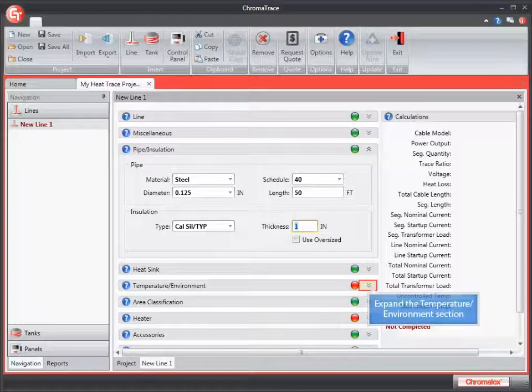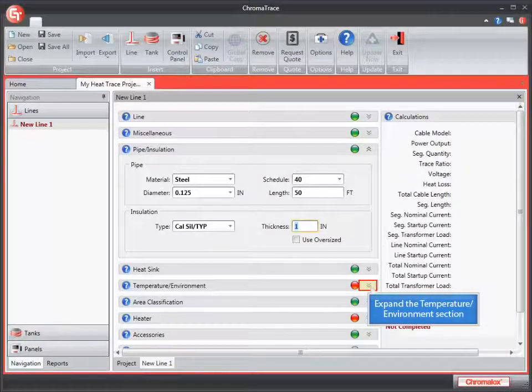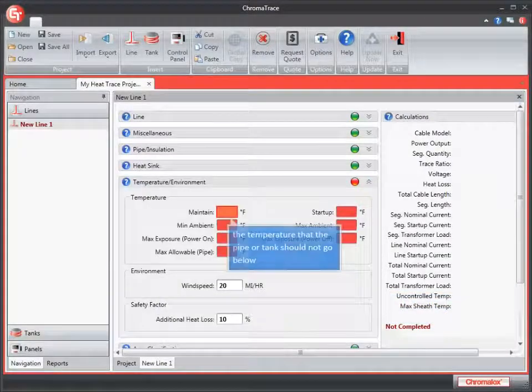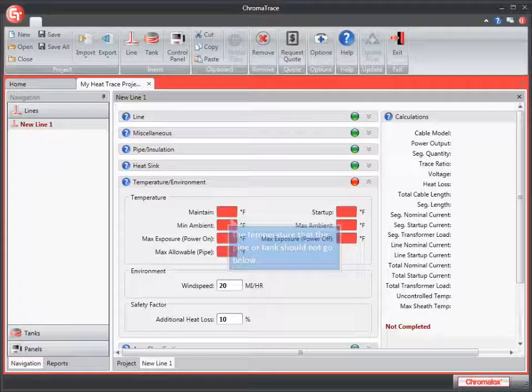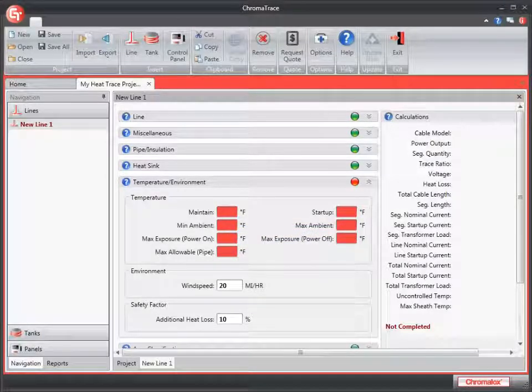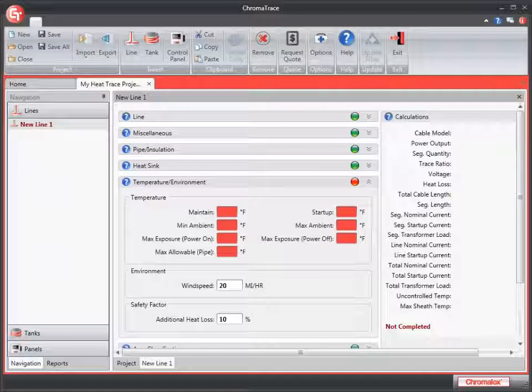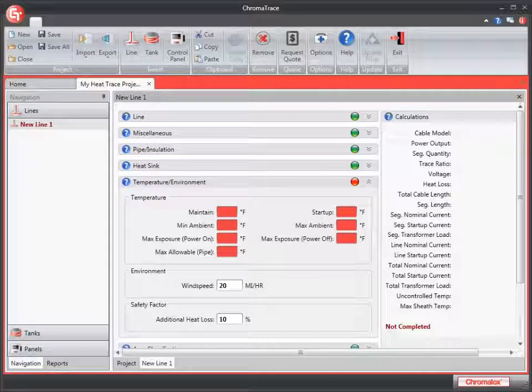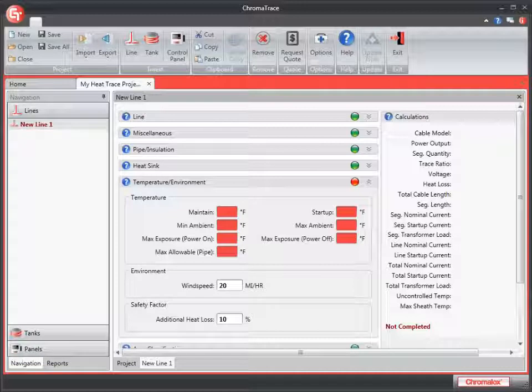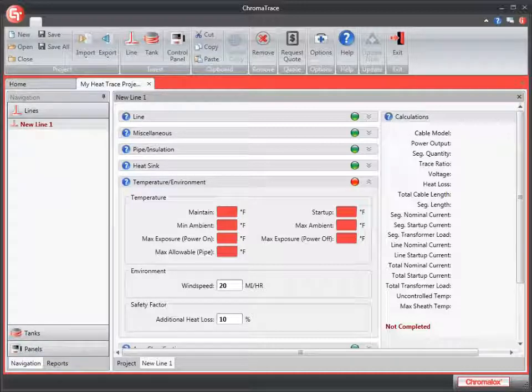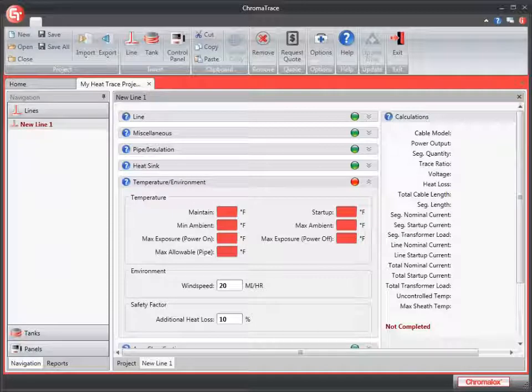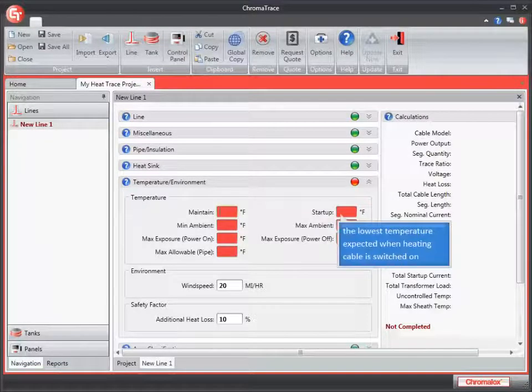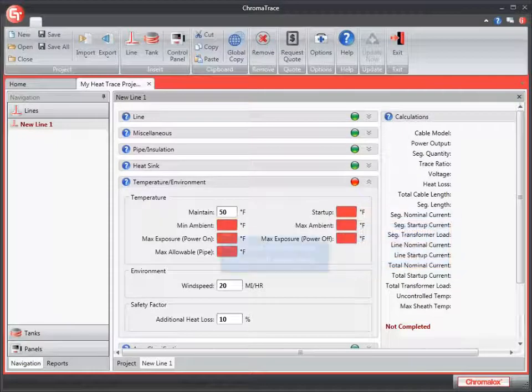Let's go to the next section that requires fields, the temperature and environment. All of the entries under the temperature section are required, so they're highlighted in red. The first field is maintain. This is the temperature that the pipe or tank should not go below. This temperature can vary with different fluids or types of processes. The temperature to be maintained cannot be lower than the minimum ambient temperature. I'm going to enter 50 for my temperature to maintain.